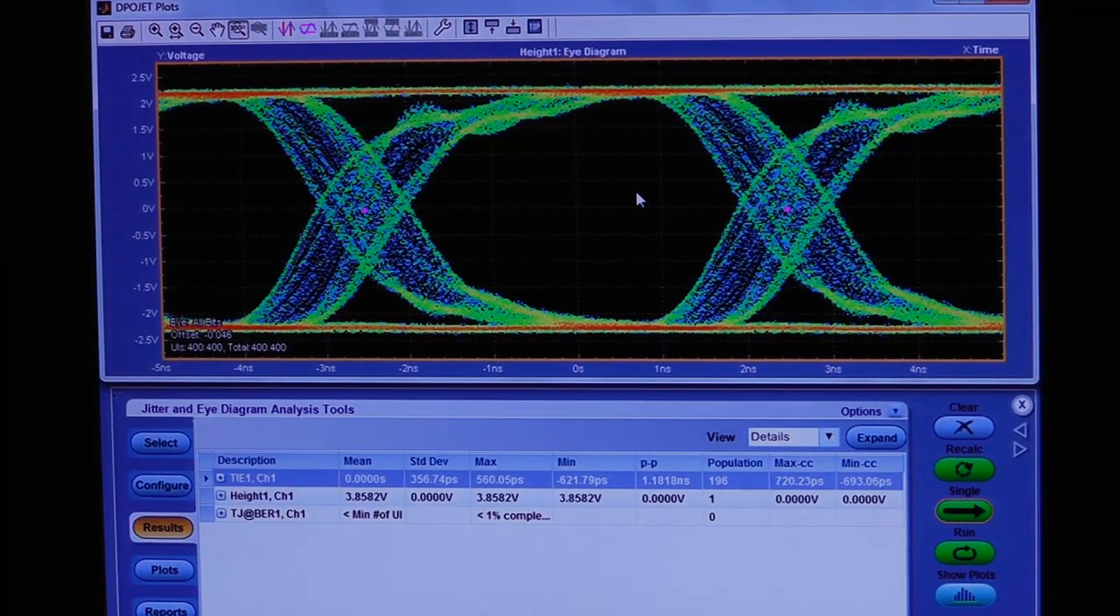Here we can see the signal folded into an eye diagram. As expected, the jitter of 0.1 unit interval is visible in the crossing section of the eye. In general, SerialXpress offers you in a simple manner to generate data signals and add multiple calibrated jitter sources.